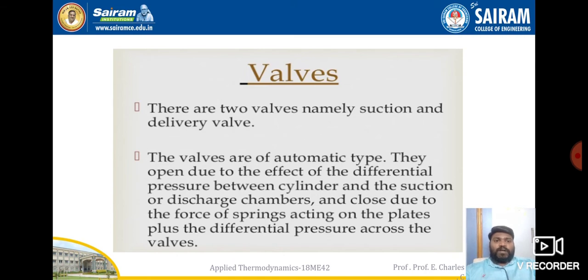See, the valves are of automatic type. They open due to the effect of differential pressure between the cylinder and the suction or discharge chambers, and close due to the force of spring acting on the plates plus the differential pressure across the valves. There will be a spring type of structure fixed on top of the inlet valves and exhaust valves.